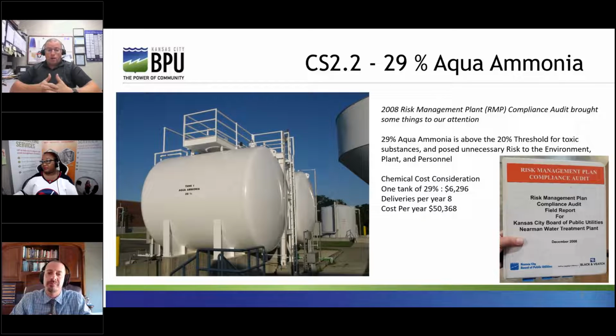and the 40 CFR requirements were a requirement for each operator to be trained and competent in operating procedures for the covered process, a requirement for refresher training at least every 3 years, and anytime updated or new procedures prior to startup of a process after a major change. A requirement to train employees involved in mechanical integrity of the process to ensure they can perform their jobs and tasks in a safe manner. And they should also be trained in hazards of each process and how to avoid or correct unsafe conditions. The main one here being a review of those items every 3 years and a multi-day audit with internal and external auditing.